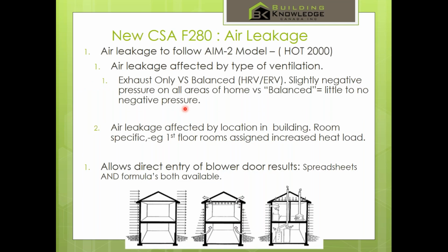The air infiltration is done using the Alberta infiltration model. Air leakage is now done the way houses actually leak in Canada. And I can't stress this enough, because for the last 20, 30 years, no offense, we've been doing it the way the Americans have been doing it, using the Lawrence Berkeley Laboratory method that says when a house leaks, it leaks out all holes equally all over the place. However, we know that 75% of the year our houses leak like this, which is in the center, which is a stack effect, which means that the air is actually leaking out some holes and leaking in others. So in the new calculation, we assign the load to the rooms where the air is actually infiltrating, which means in our climate, magically enough, we're going to be assigning more heat load to be met in the basements, which may be one reason why we've not been assigning enough load in the past, because we've been doing it like they do in California.